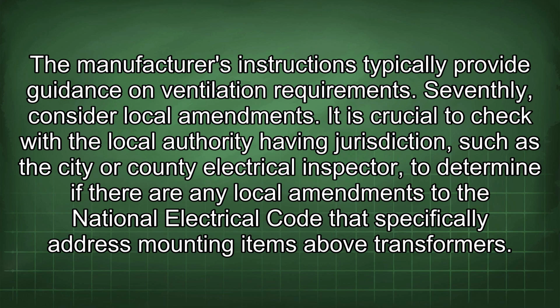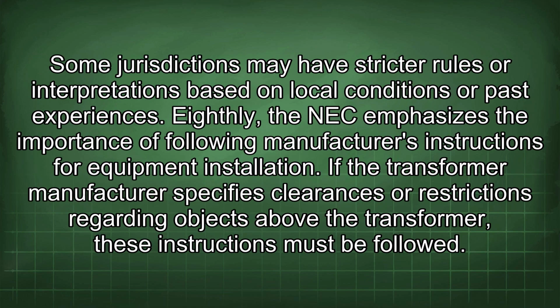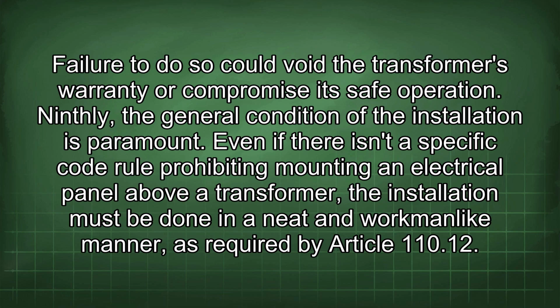Seventhly, consider local amendments. It is crucial to check with the local authority having jurisdiction, such as the city or county electrical inspector, to determine if there are any local amendments to the National Electrical Code that specifically address mounting items above transformers. Some jurisdictions may have stricter rules or interpretations based on local conditions or past experiences. Eighthly, the NEC emphasizes the importance of following manufacturer's instructions for equipment installation. If the transformer manufacturer specifies clearances or restrictions regarding objects above the transformer, these instructions must be followed. Failure to do so could void the transformer's warranty or compromise its safe operation.